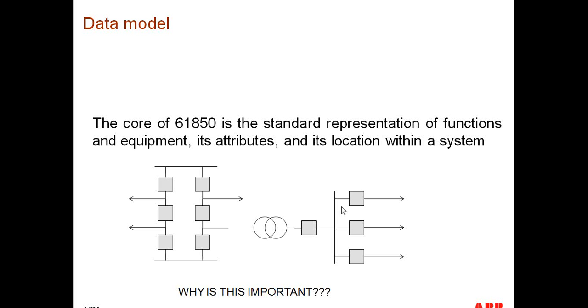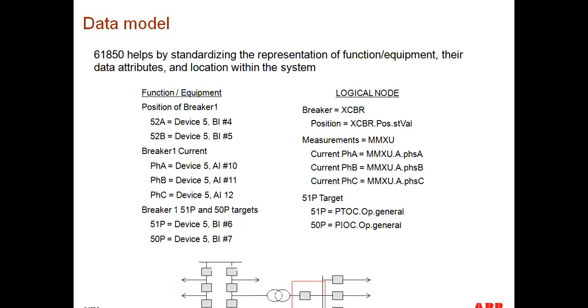So now let's just take the example of the position of the breaker. When you look at a protocol such as DNP or Modbus, the position of the breaker is really represented by those protocols as a binary input and status point. There's really no framework defined by DNP or Modbus that says that particular binary input is the position of a breaker. And that's where integration comes into play, which is having to make that association between the power system, or the actual application, and the protocol, and then making use of that information.